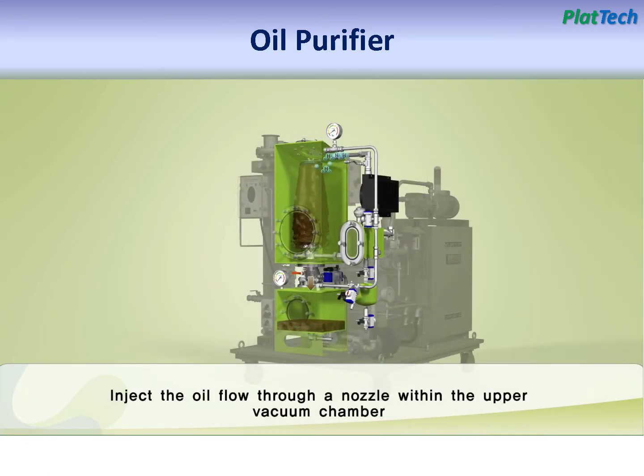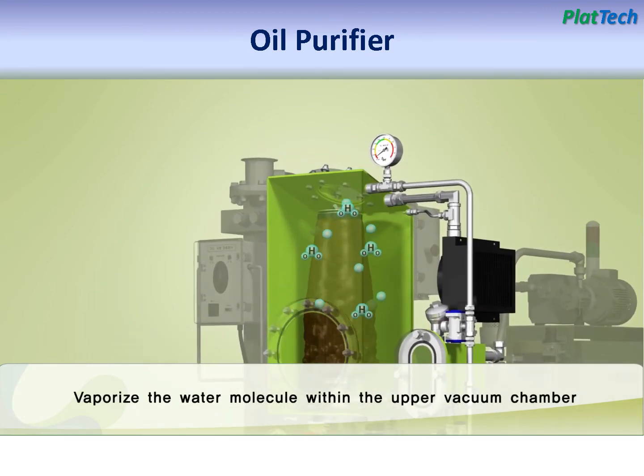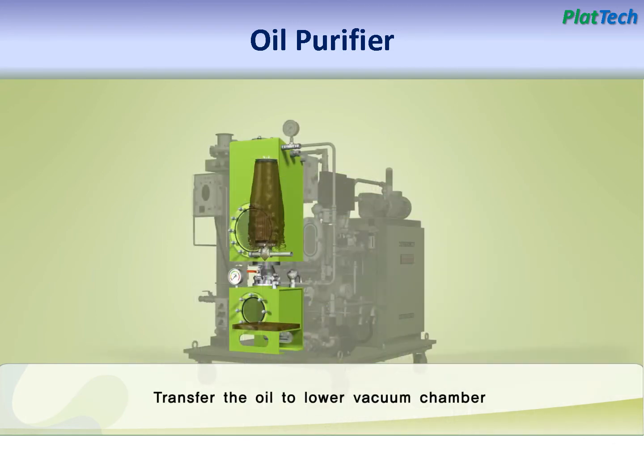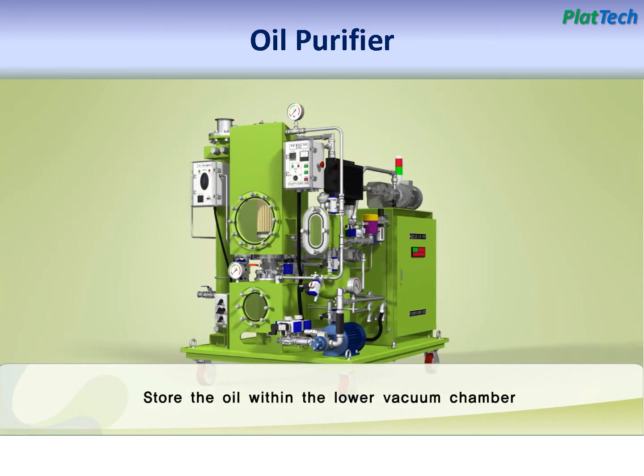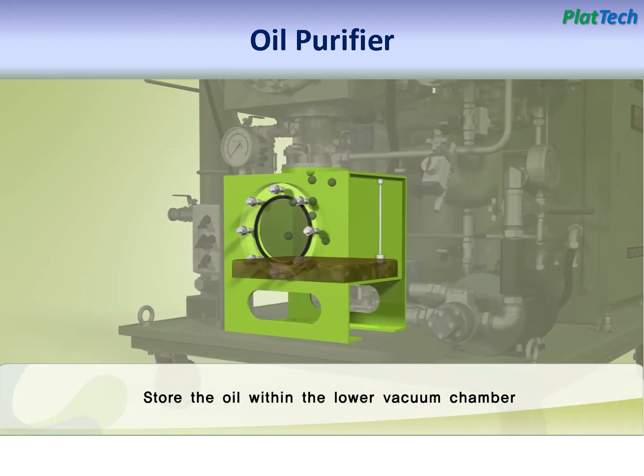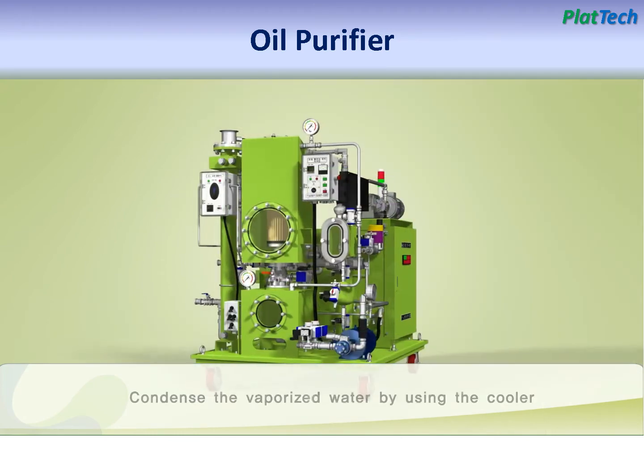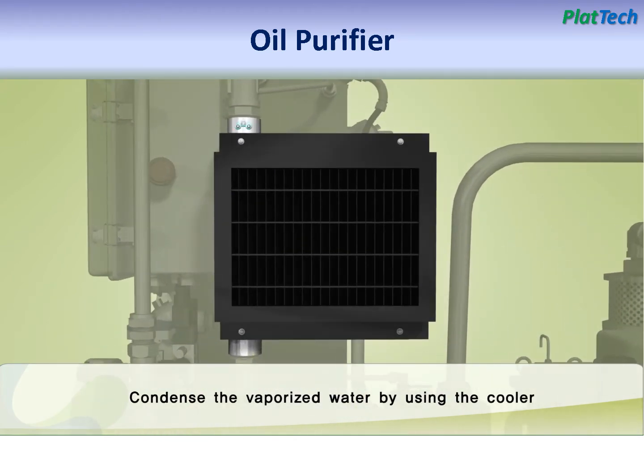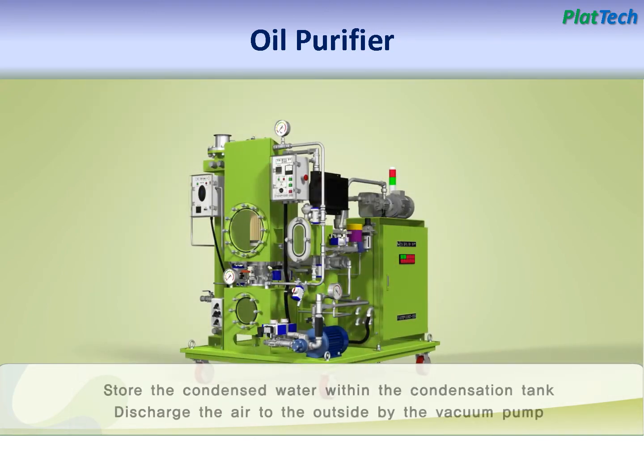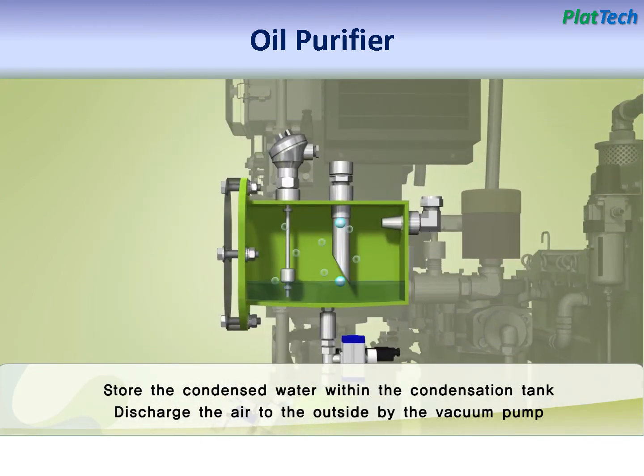After injecting oil through a nozzle in the upper vacuum chamber, dissolved moisture and gases are evaporated. Oils will be transferred from the upper chamber to the lower chamber. Evaporated water will be condensed and stored to be discharged automatically.